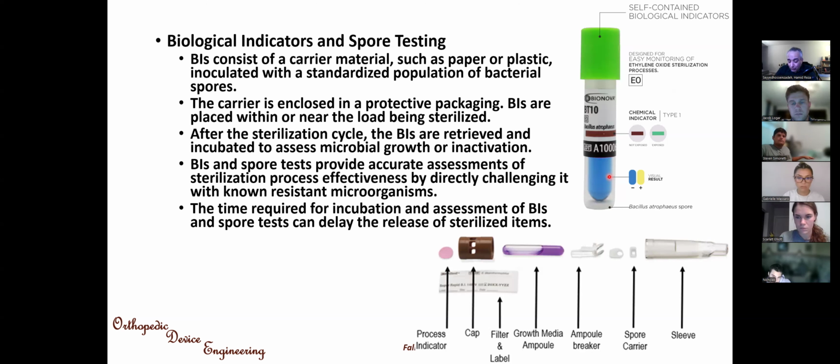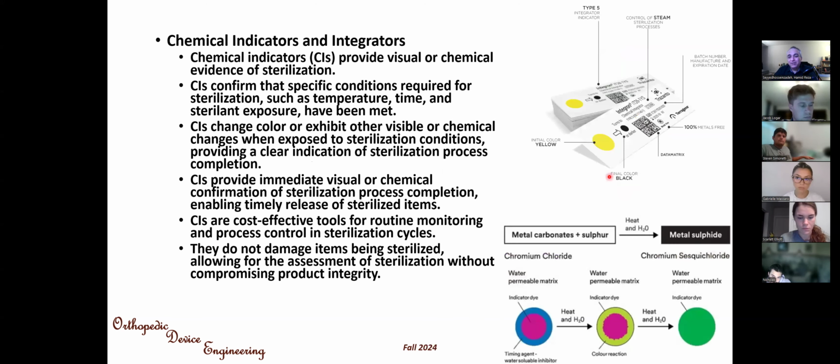But if you want to become sure when you want to perform the surgery to see if the package item is sterile, you have another option, and that's chemical indicator. These are some chemicals that, based on the technique of sterilization you are using, when all the conditions necessary for sterilization is fulfilled, this chemical indicator changes in color to a specific color.